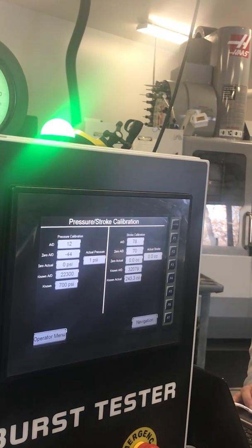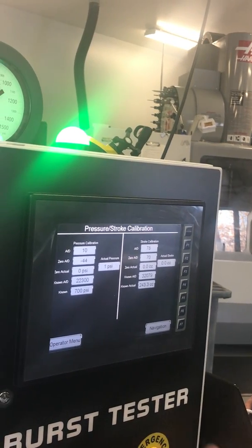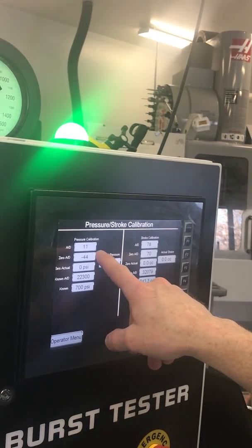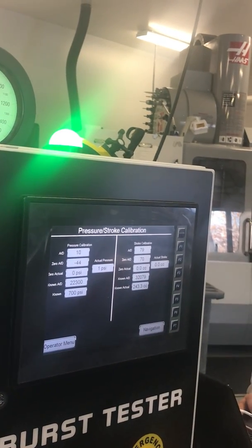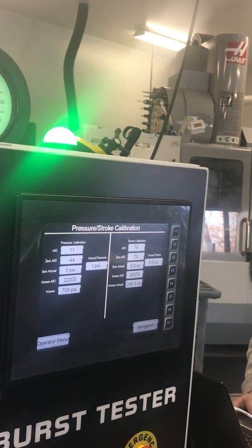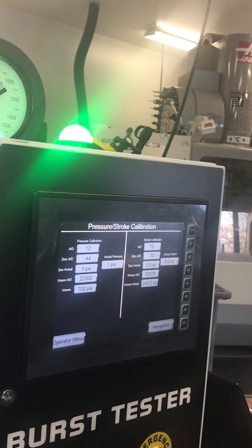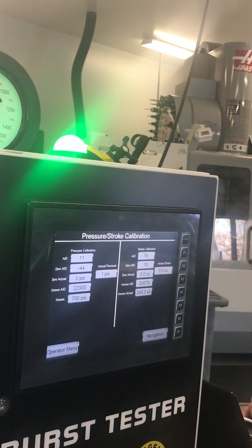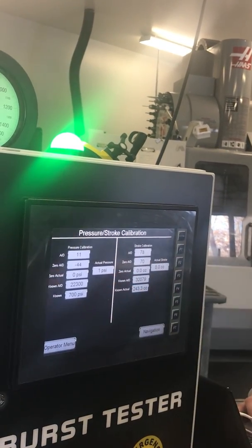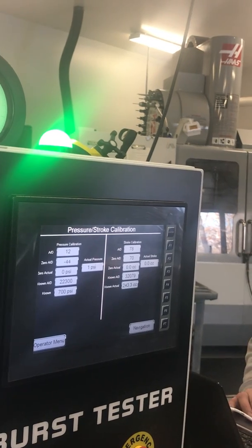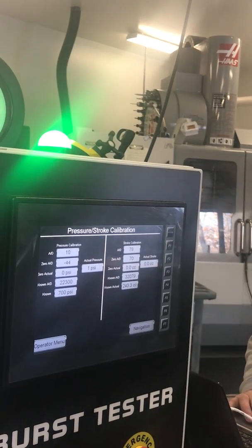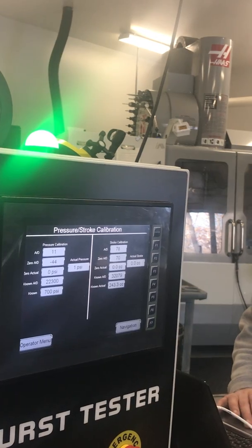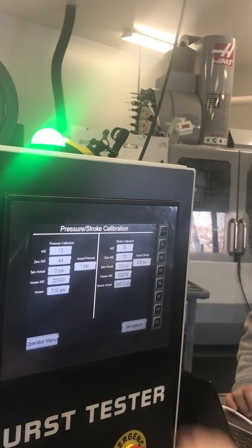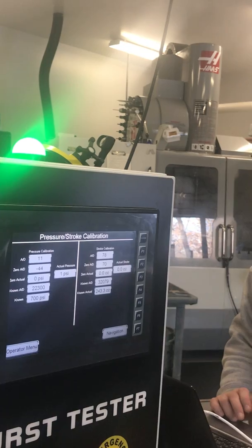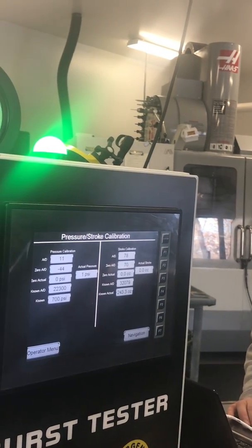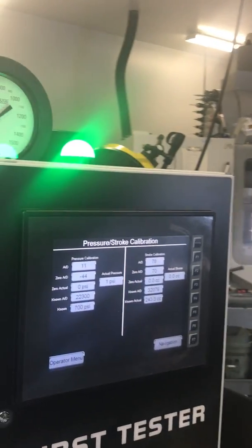And so what you're doing is you're saying, you know what 0 is? Right now we're dithering at 11, 12. So digitally, it's trying to say we're right there. That's what I'm reading. You want to call that 0 PSI? Be my guest. Now you've just said that digital input is now 0 PSI. Then you bring it up to pressure, and again, you'll see this number is now like 23,000 or something. You'll enter that number in here, and then enter. And so you've actually locked 0 and span in whatever pressure you were at. Clear as mud.